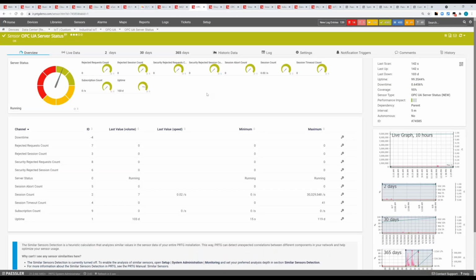I think, as I showed you, OPC UA is really the big deal. When you go to the OT environments, it's really the interoperability standard. Therefore, we integrated a specific sensor type, the OPC UA server status, because it's very obvious that when you want to enable communication, you need to make sure the most important part is working, and this is definitely the server status. So we can show everything is green, no need to check further. But we can also pinpoint the warning states, whether there was a shutdown, a failed request, or a communication fault.